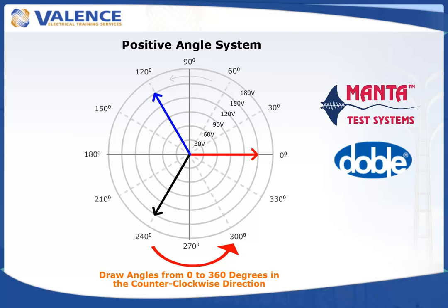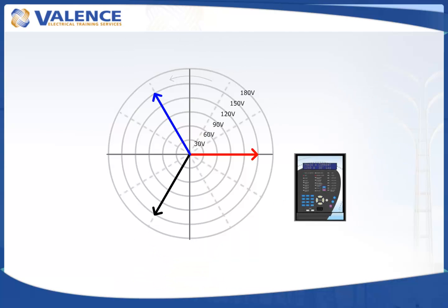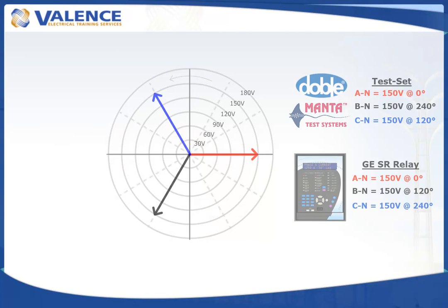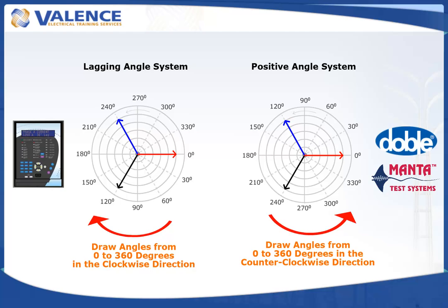If you generated the following voltages in a GE SR relay with a DOBLE test set, your test set would report these angles, but your relay would report these angles. It looks like you're generating ABC rotation from your test set, but the relay is receiving ACB or vice versa depending on your background. If you look at the correct angle system used by each device, you can see that the phasors don't move, it's the angles that are relabeled in each device.